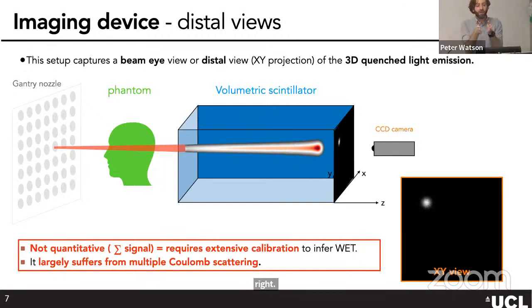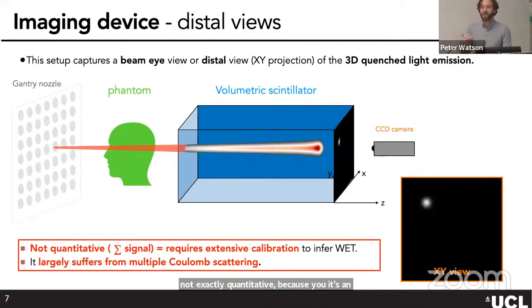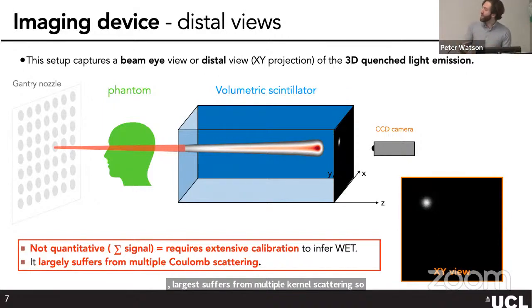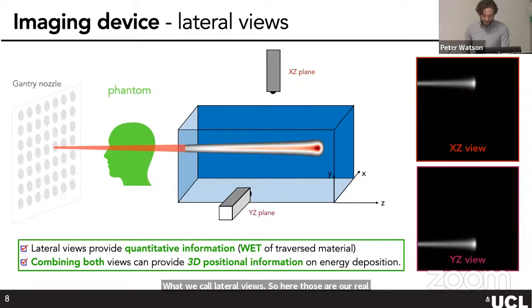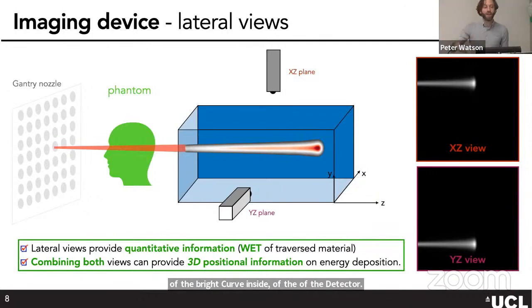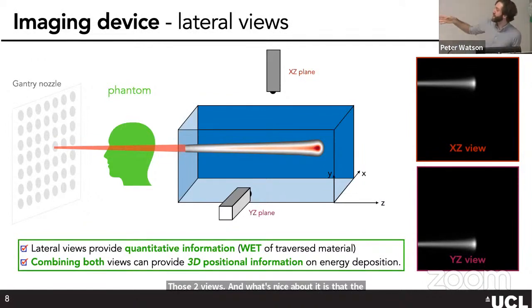The most common approach is placing a CCD camera at the distal end of the scintillator, which integrates all light along the beam spot. However, this suffers greatly from multiple Coulomb scattering — protons scatter a lot inside human tissues — leading to very blurry images. The better approach is using lateral views, where you get 2D views of the Bragg peak inside the detector. Our setup uses two lateral views — a top view and a lateral view.